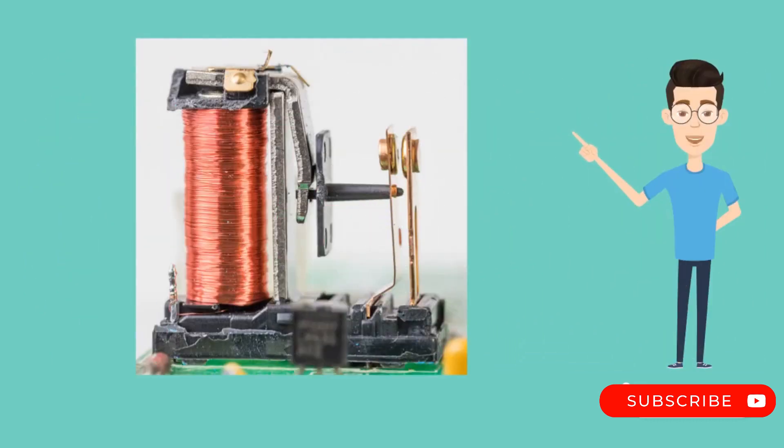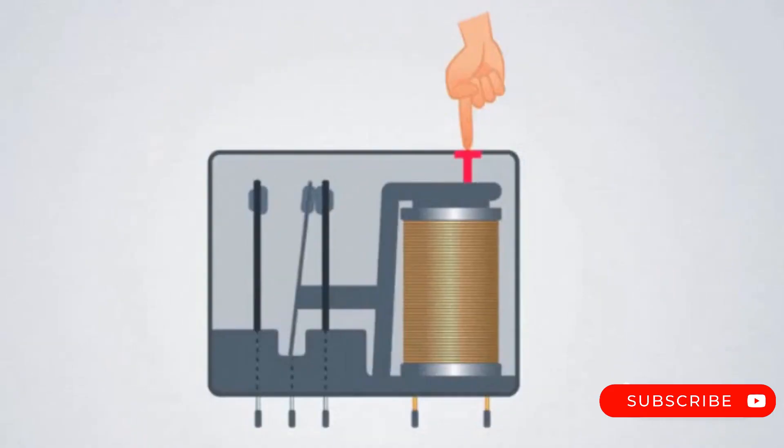Magnetic coil relays, on the other hand, use an electromagnetic coil to control the switch. When a current is passed through the coil, it creates a magnetic field that attracts a metal plate, closing the circuit and allowing current to flow. And in this way the contacts of the relay switches between normally open and normally closed.